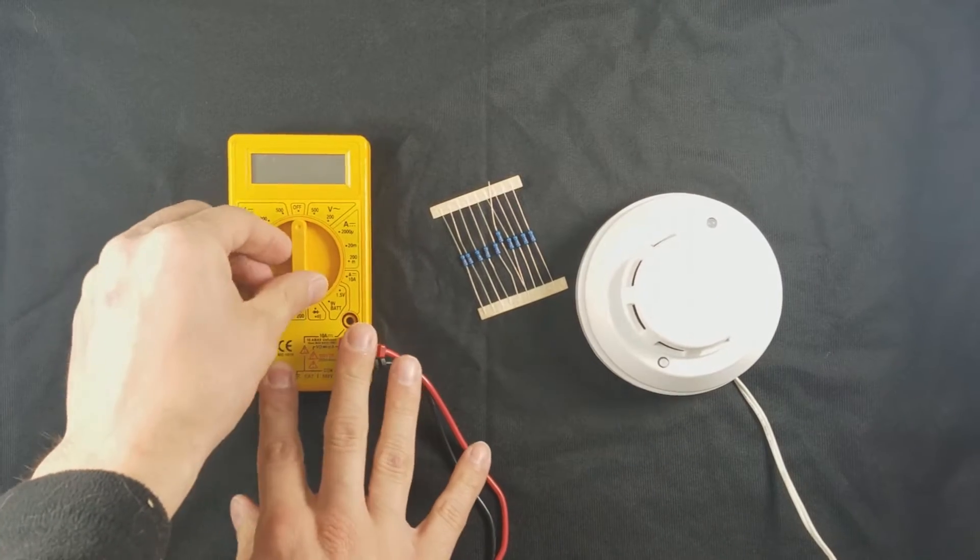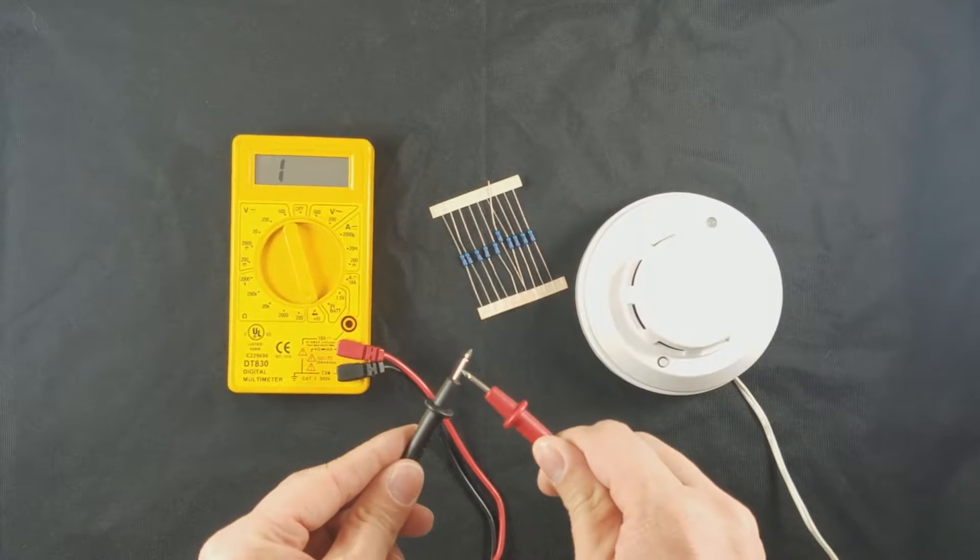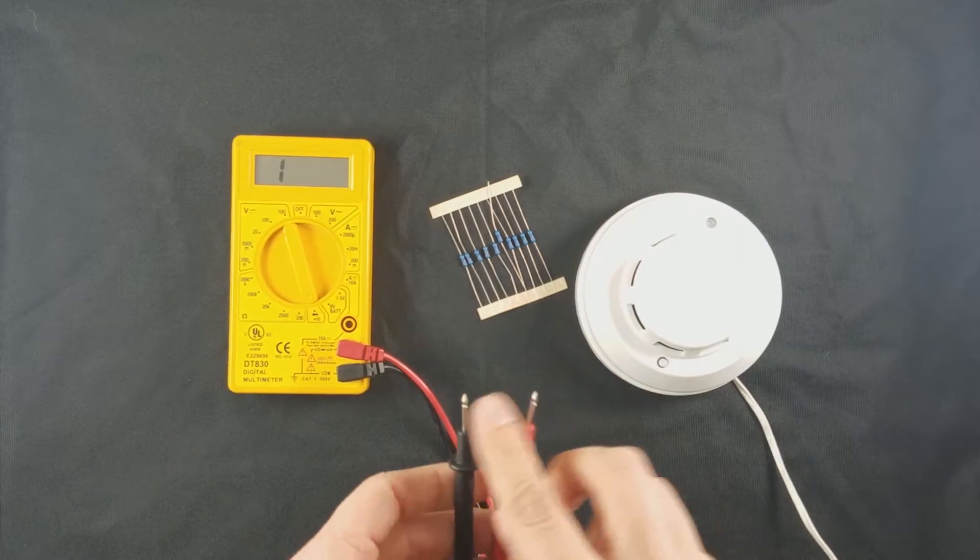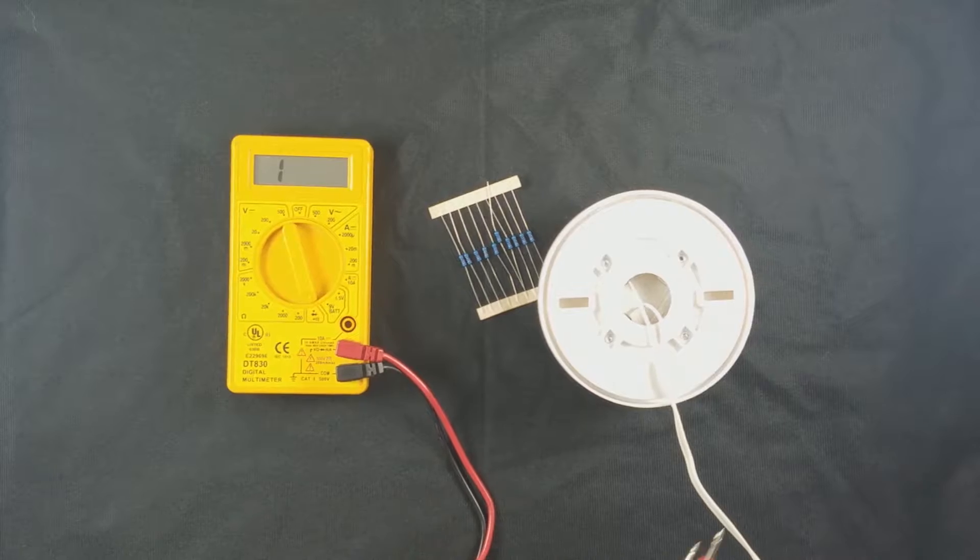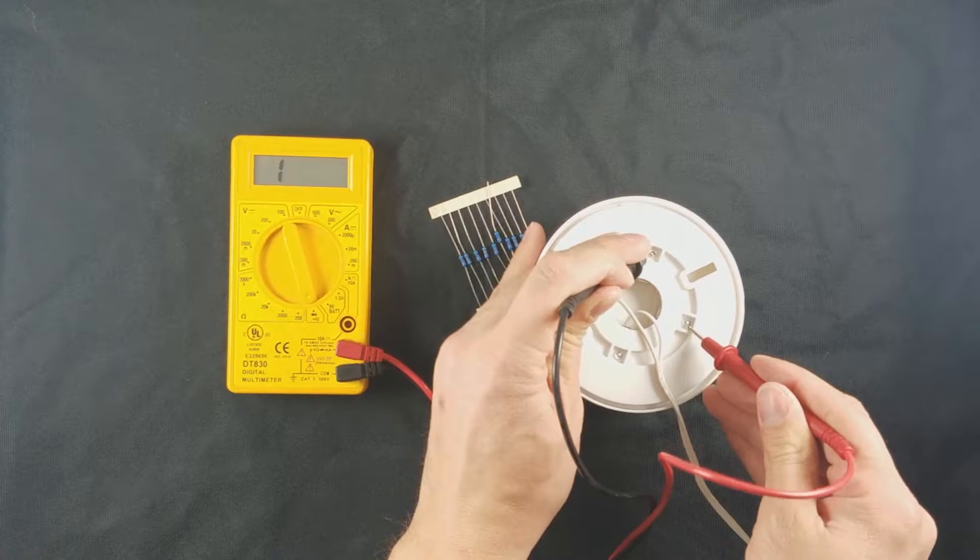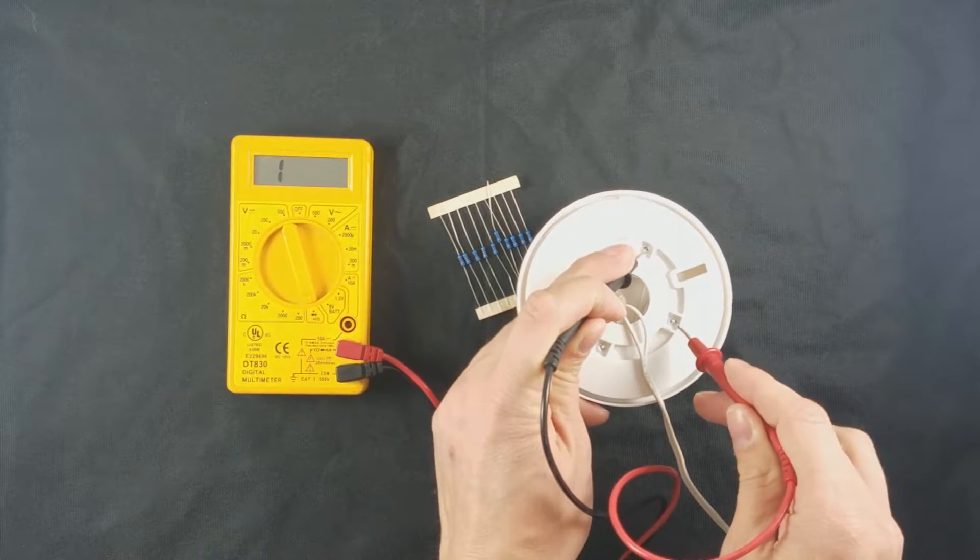With this multimeter, I'm going to turn it to the continuity setting, so it will beep when the two terminals touch. I'm going to flip the smoke detector over—these are the two relay terminals. When you touch them, you can hear it's currently set to normally closed because it's beeping.